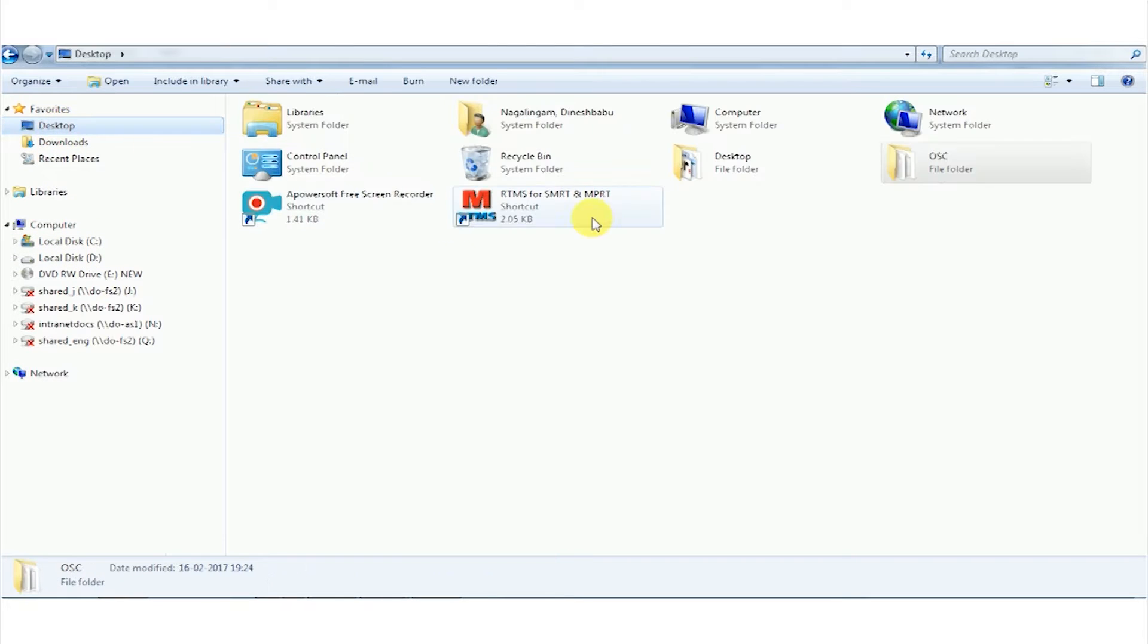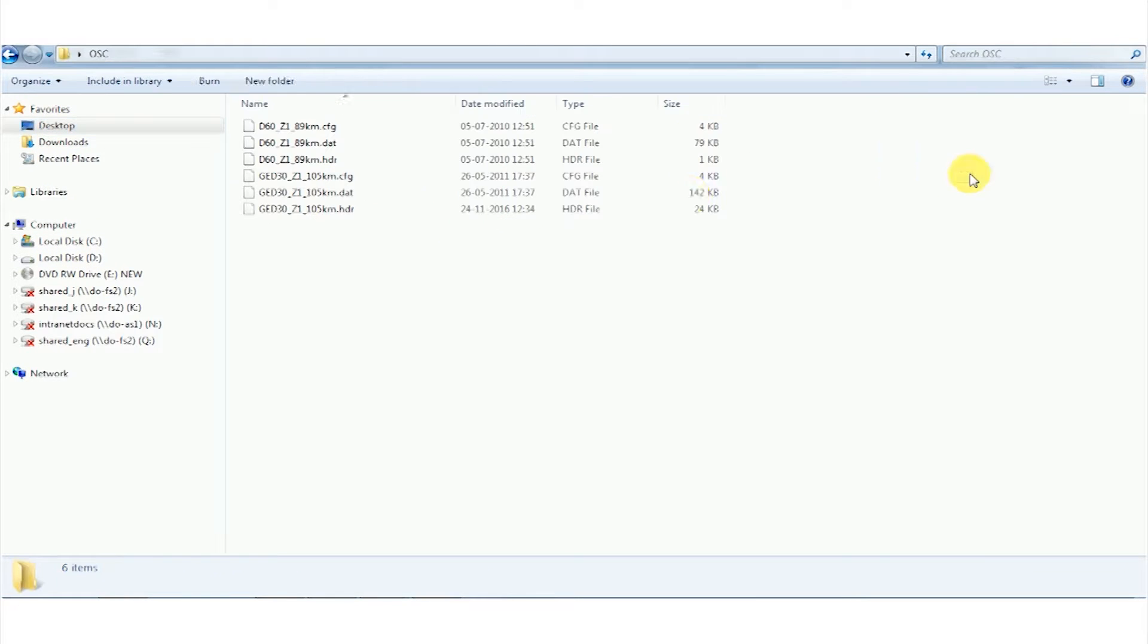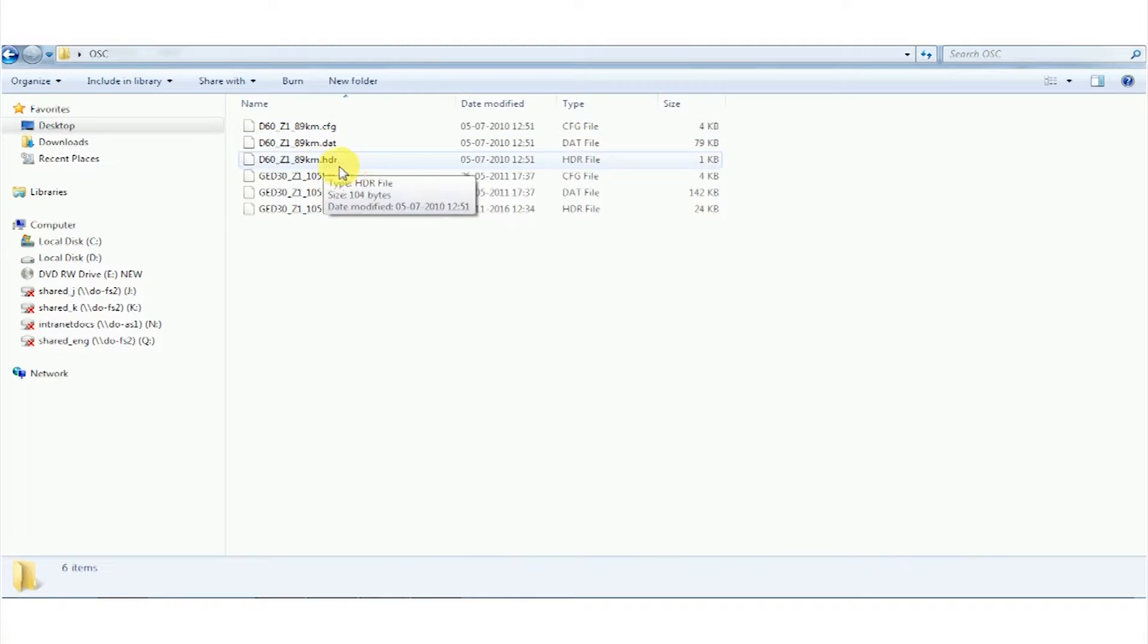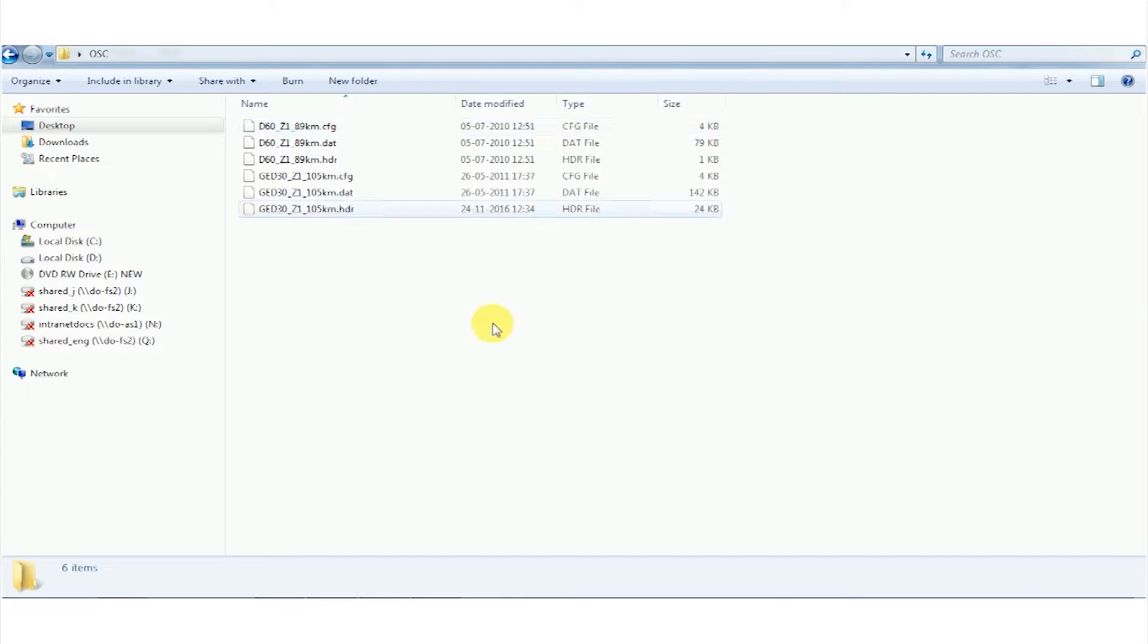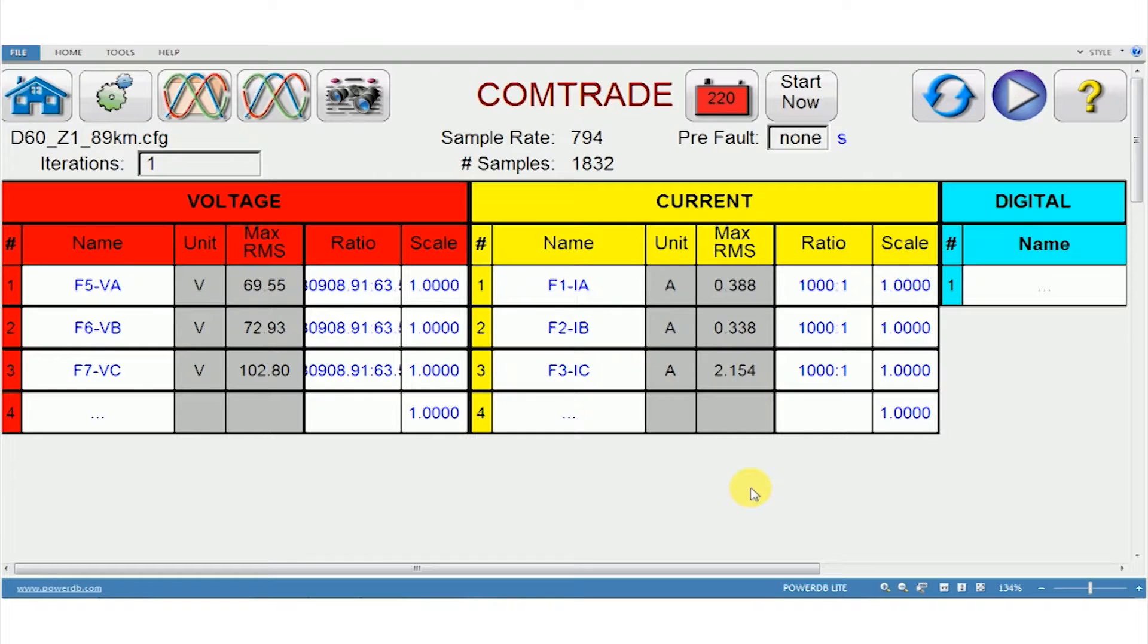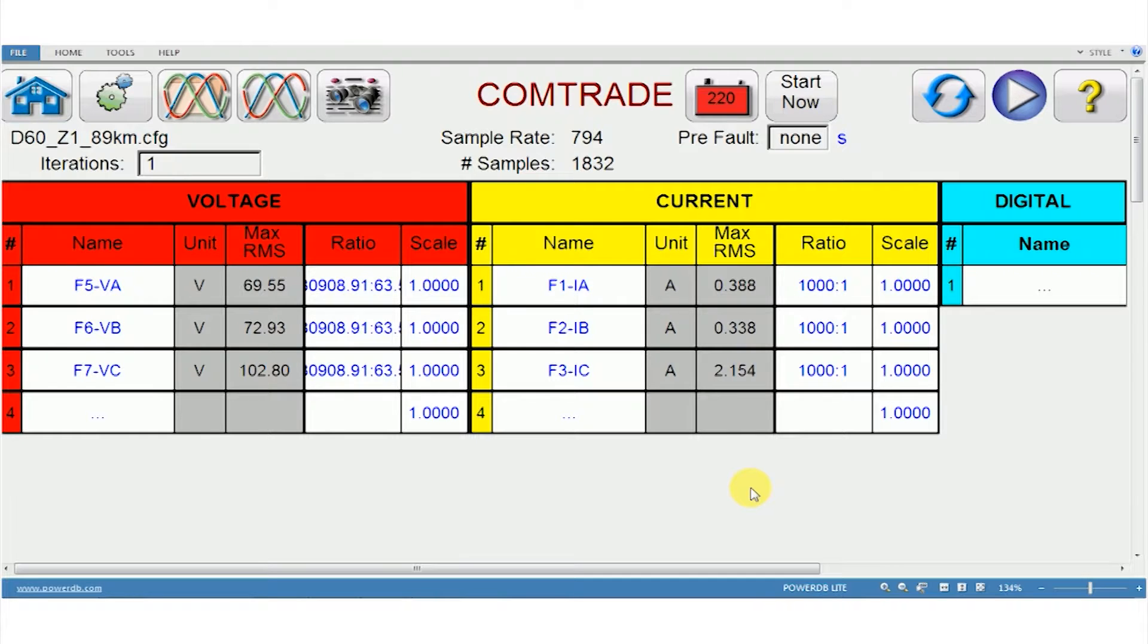When I go to the desktop in the oscillograph folder, CFG, DAT and HDR, all three files come together. If only the CFG file is available the test kit cannot play back. So that's the universal format, all three files have to come together.